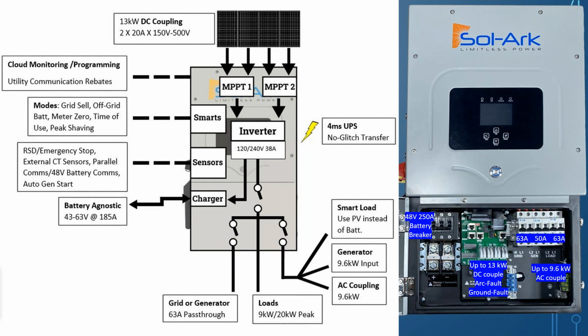Not to rain on your presentation, but some things on this slide I particularly love about the Sol-Ark inverter: that well-sized 63 amp grid pass-through is a little larger than the competition, and that allows you to supply a lot of grid-tied power onto the critical load panels, so you can put a little more juice on the critical loads. That's really nice.